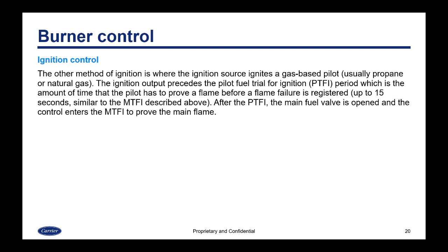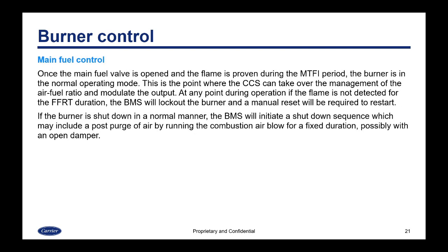The other method of ignition is where the ignition source ignites a gas-based pilot, which is usually propane or natural gas. The ignition output precedes the pilot fuel trial for ignition period — the amount of time the pilot has to prove a flame before a flame failure is registered — which is again up to 15 seconds, similar to the MTFI. After the PTFI, the main fuel valve is opened and the control enters the main trial for ignition to prove the main flame. Once the main fuel valve is opened and the flame is proven during the MTFI period, the burner is in normal operating mode, where the CCS can take over air-fuel ratio control and modulate the output.